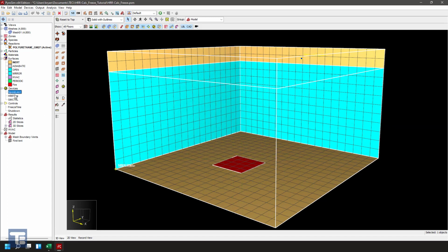So you can see I have my Sprinklink. I've got my heat release rate time, which is a time output device. I've got my sim control, which is going to shut it down when the sprinkler link activates. I have 2 controls. I have a freeze time control, which is just set up to stop updating the heat release rate time output when the sprinkler link activates, and a shutdown, which will activate the sim control device 20 seconds after the link activates. So I have everything I need now in the simulation.